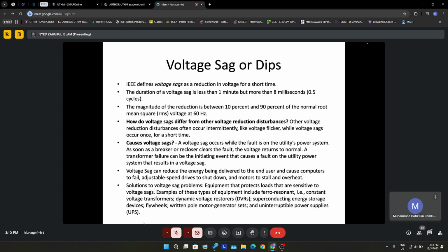The voltage reduction disturbance is different from the voltage sag. The voltage reduction disturbance happens frequently or periodically, coming suddenly. That is the reduction disturbance. But voltage sag usually occurs once, and for a very short time. So that one time can spoil everything.